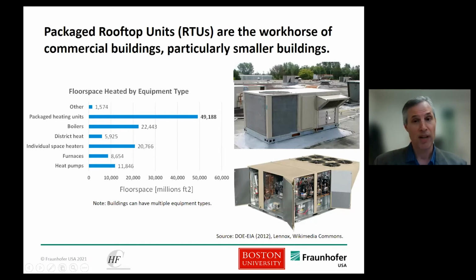Here's, for example, an outdoor air damper, and everything's contained in this box. Real estate is really precious here. If you start changing the size of this box, then you have to change the size of the curb, and then you have to do a new integration with the building, which increases its costs. But overwhelmingly, if you look at estimates for energy consumption for the commercial building sector in terms of HVAC, roughly 60% is in these packaged rooftop units.